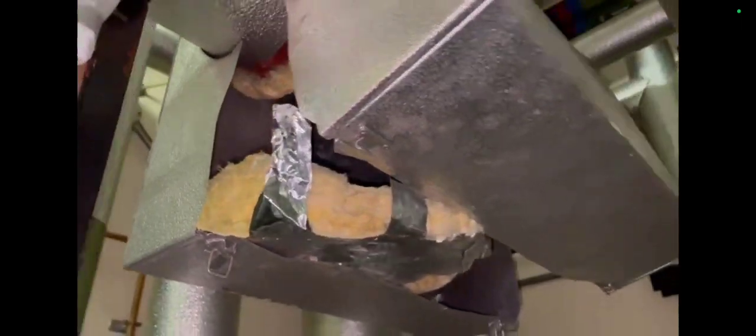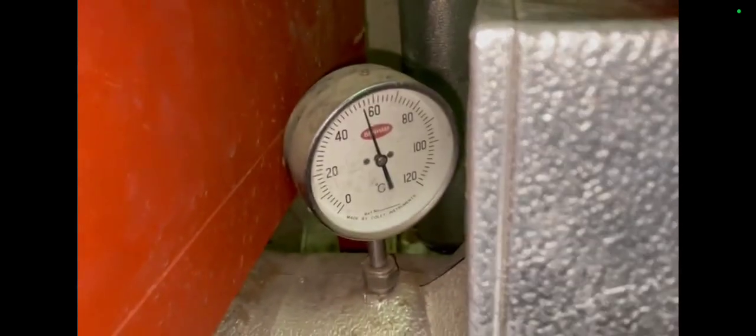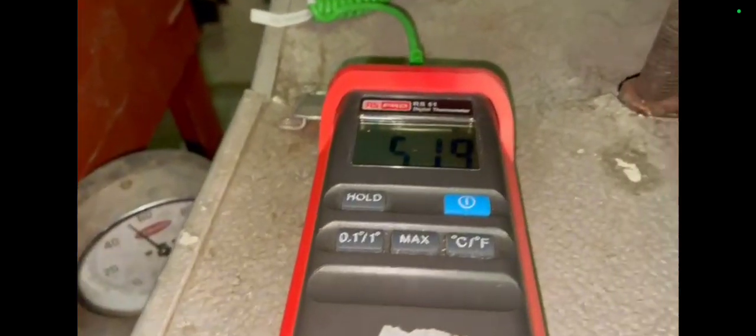So here is the strainer inside this casing here, quite a big one. That's going to need cleaning out. I'm just there checking if my gauges are actually correct because there's no guarantee that they are. Okay, that job got put down to the strainers needing taking out and cleaning or replacing. I'll get back to you on that one.